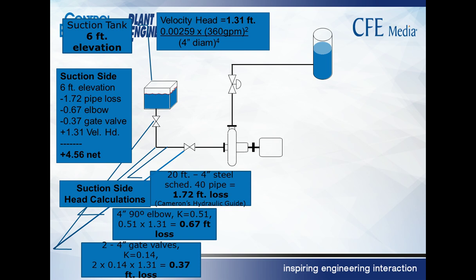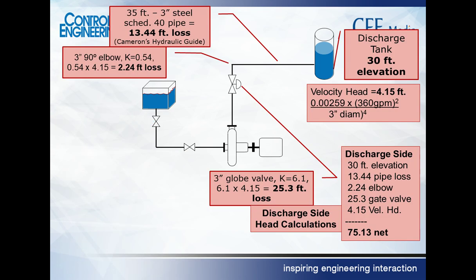Got to add a little bit of velocity head in, and we end up with a little over 4.5 feet of head net for the suction side. Let's do the same thing for the discharge side. And incidentally, that's at 360 gallons per minute.